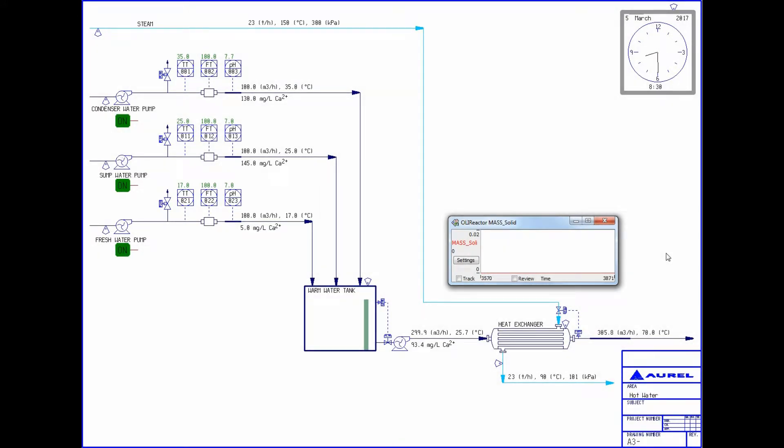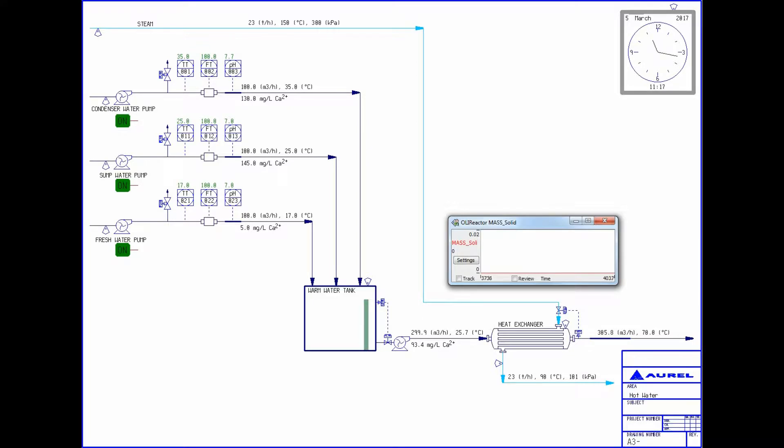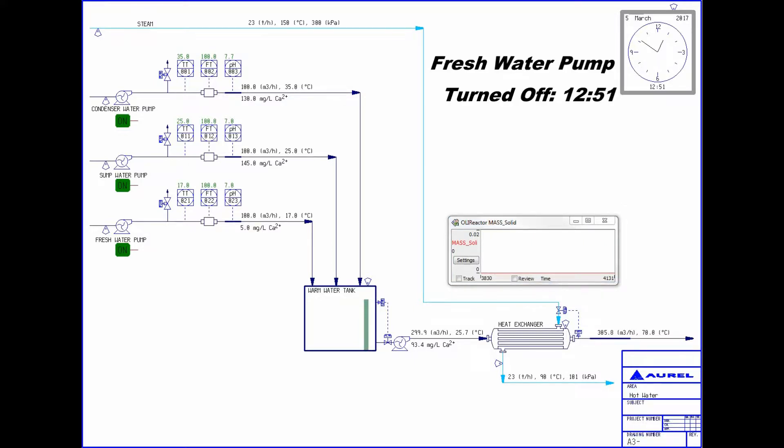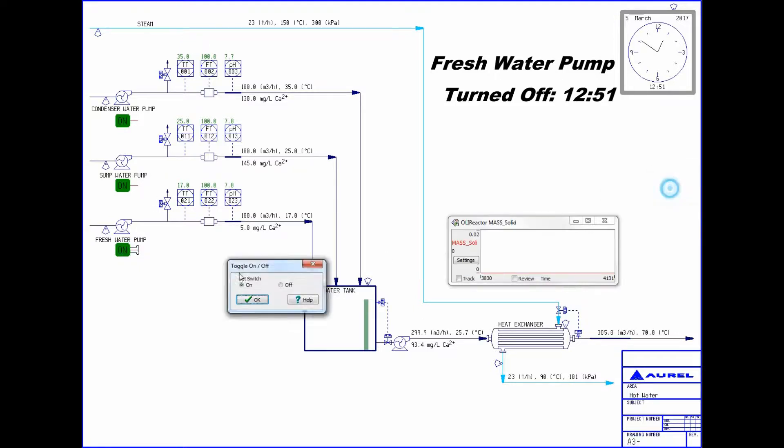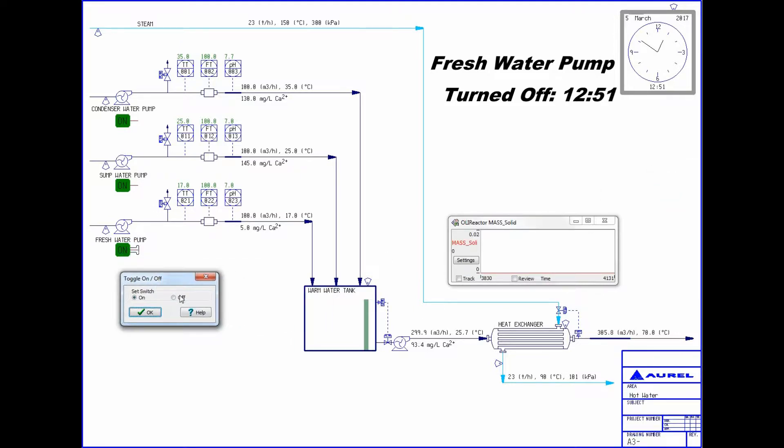In this scenario, I am going to turn off the fresh water pump to mimic it being taken out of service. I want to see how long it takes for the concentration of calcium in the warm water tank to reach a level high enough that scaling begins to form through the heat exchanger. To begin this, I paused the simulation and made a note of the time. Now I will select the on-off switch for the fresh water pump and turn the pump off and run the simulation again, watching for solid to begin forming.